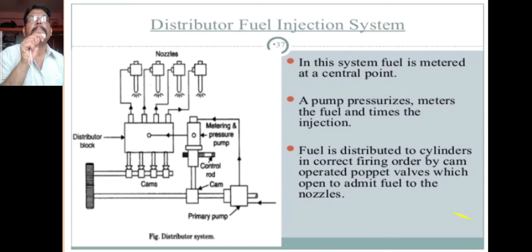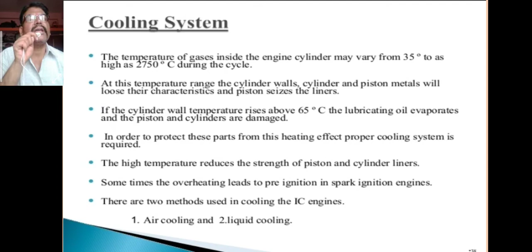Now the cooling system for the diesel power plant. The temperature of gases inside the engine cylinder may vary from 35 degrees to as high as 2750 degrees centigrade during the cycle. At this temperature range, the cylinder walls, cylinder and piston metals will lose their characteristics and the piston seizes the liners. If the cylinder wall temperature rises above 65 degrees centigrade, lubricating oil evaporates and piston and cylinder are damaged. In order to protect these parts from the heating effect, a proper cooling system is required.